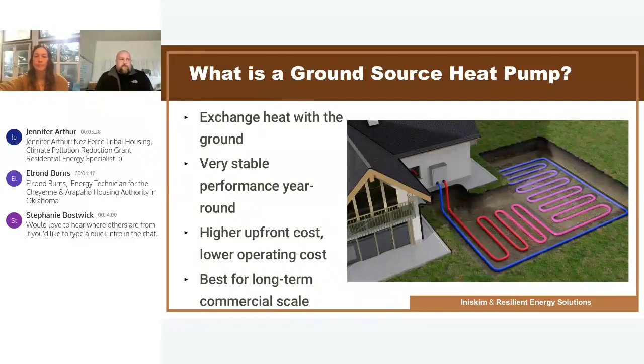Ground source systems take advantage of the fact that about 10 feet below the surface of the earth, almost everywhere on the planet, it's a pretty consistent 55 to 60 degree Fahrenheit temperature. In these applications, typically a 2 to 6 inch pipe is laid out as seen in the picture, and it circulates water - in cold climates it will have some antifreeze solution mixed in - using the earth to cool the temperature to 60 or heat to 60, depending on environmental conditions at the time. This technology tends to work best in environments that get either much colder than 60 or much hotter than 60 degrees. Next slide, please, Steph.